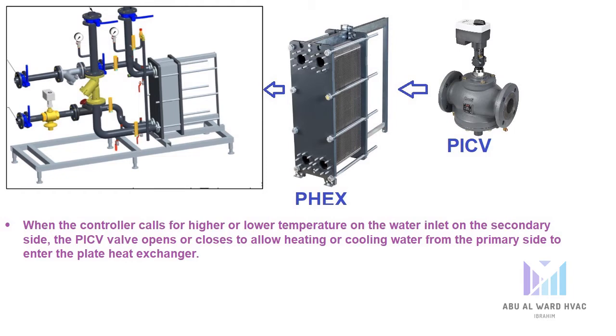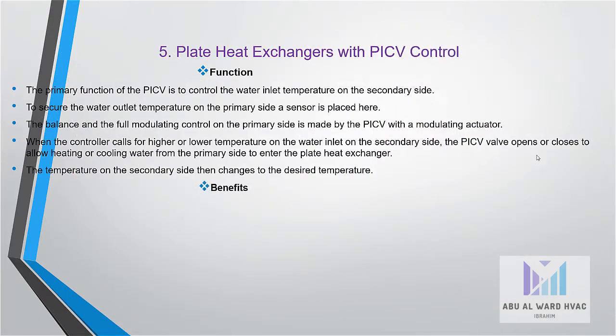The balance of the full modulating control on the primary side is made by PICV with a modulating actuator. When the controller calls for higher or lower temperature on the water inlet on the secondary side, the PICV valve opens or closes to allow heating or cooling water from the primary side to enter the plate heat exchanger. The temperature on the secondary side then changes to the desired temperature.